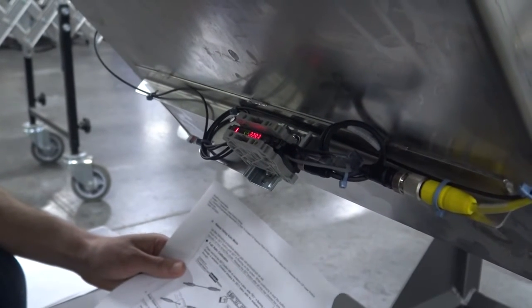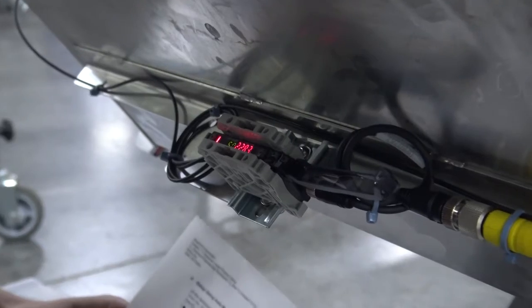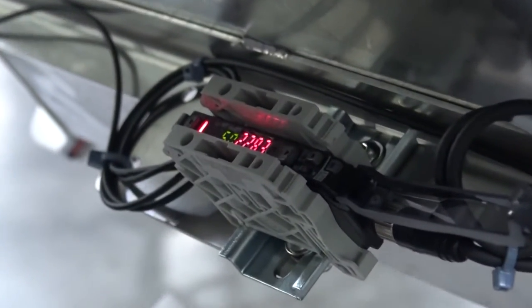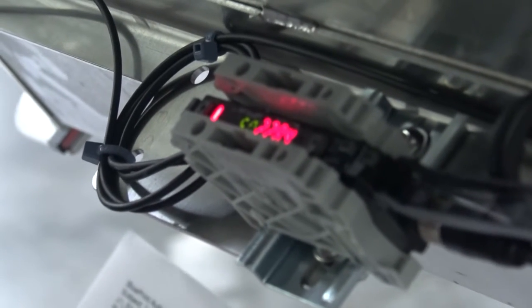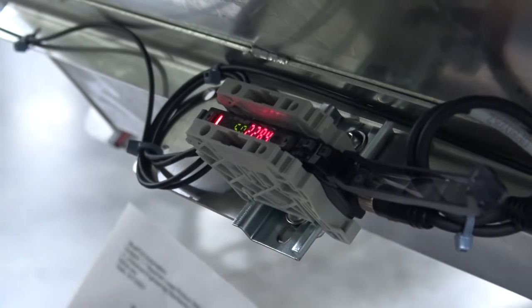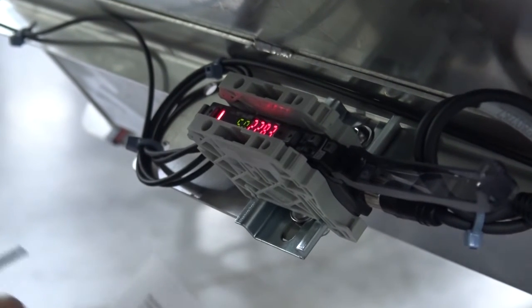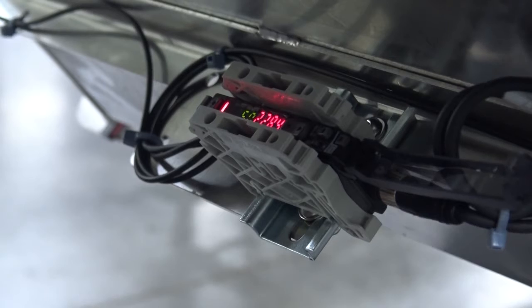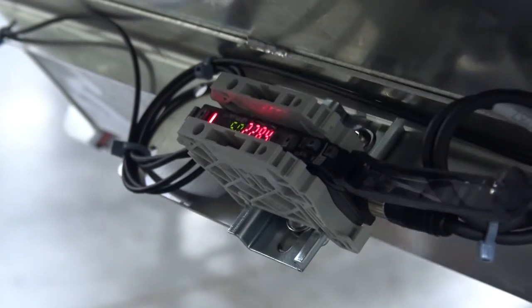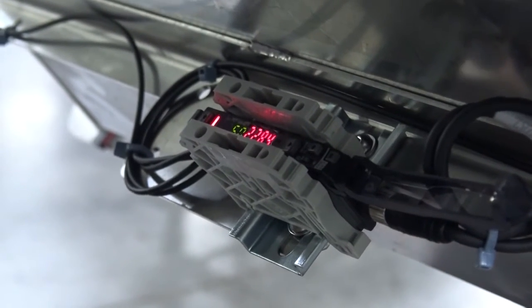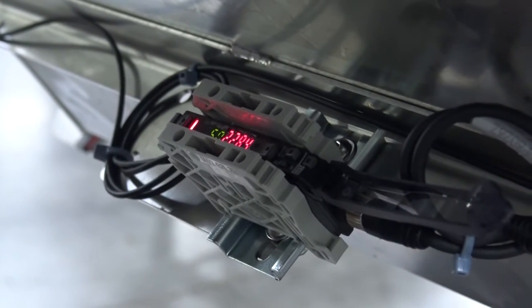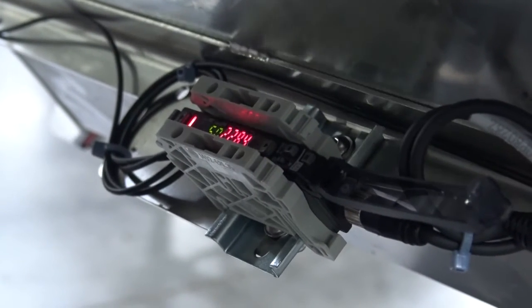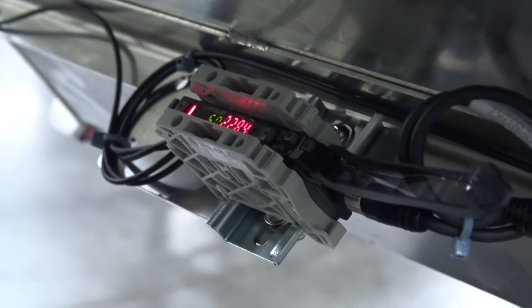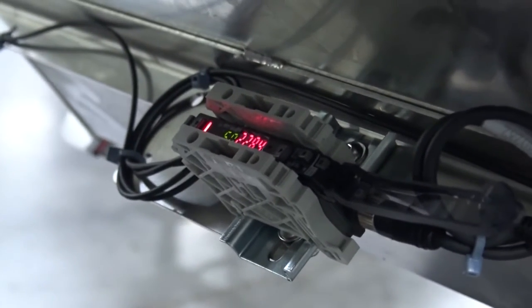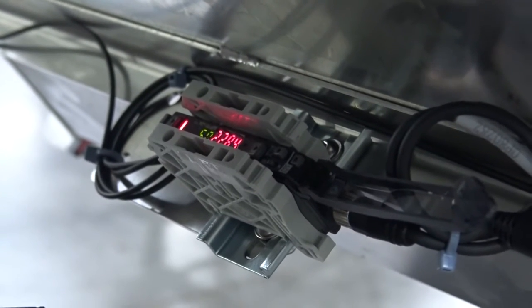Okay, next one is going to be to calibrate, and we're going to do a dynamic calibration. The way to do that, according to the procedure, is to press and hold the set button, and you're going to see the set blinking. You're going to continue to hold that, and then you're going to drop product through the sensors and that'll give you a live dynamic calibration. I'm going to drop as many French fries as I intend to calibrate the sensors to, and then once I've done that, I let go of the set button, and then it'll automatically calibrate.